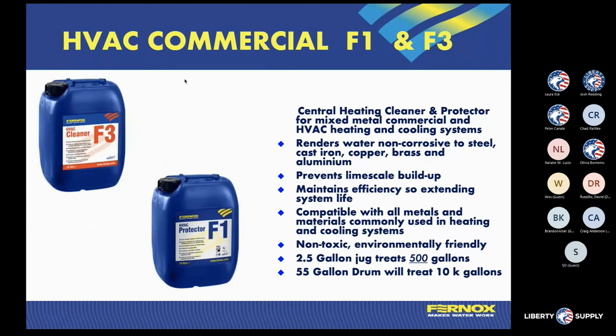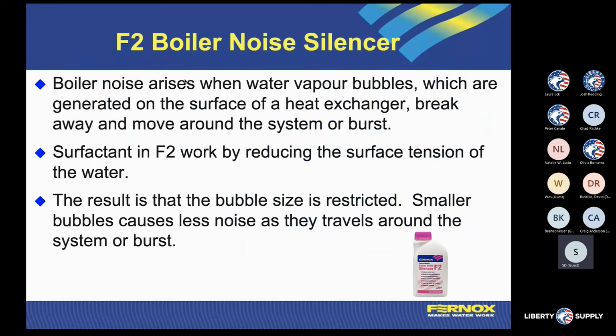So we have the F1 and F3 product in not only the residential sizes, but we also mentioned we have larger sizes for commercial applications. We have a 2.5 gallon jug of the cleaner and the inhibitor, and they also have a 55-gallon drum. The 2.5 gallons will do 500 gallons, and the 55-gallon drums will do 10,000 gallons. If we're doing the filter fluid, we make that in a 5-gallon pail, and that will do 500 gallons of system fluid.